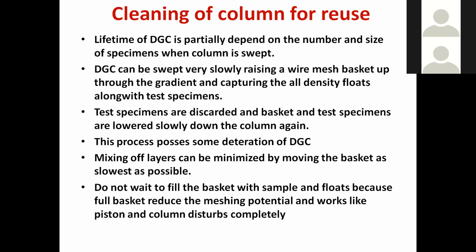So, the lifetime of a density gradient column partially depends on the number and size of specimens when the column is swept. The density gradient column can be swept very slowly, raising a wire mesh basket up through the gradient and capturing all the density floats along with the test specimens.